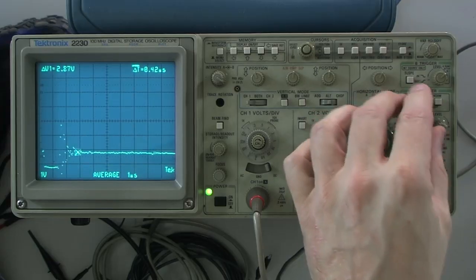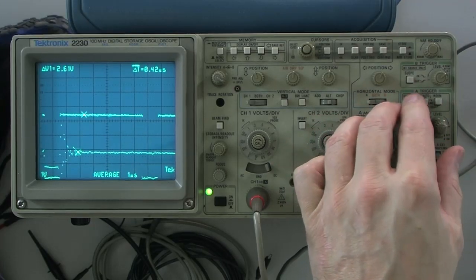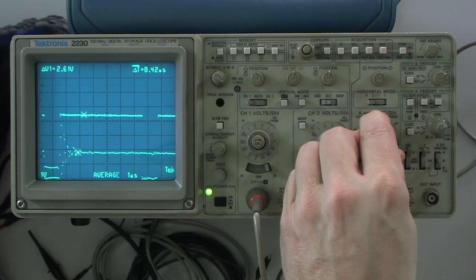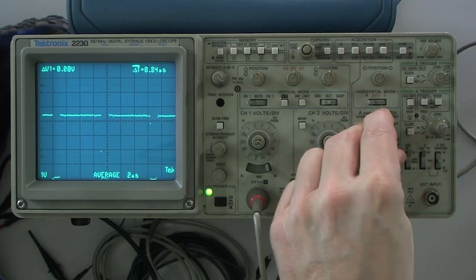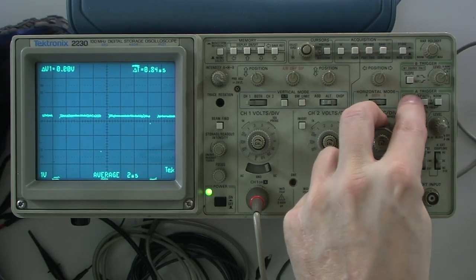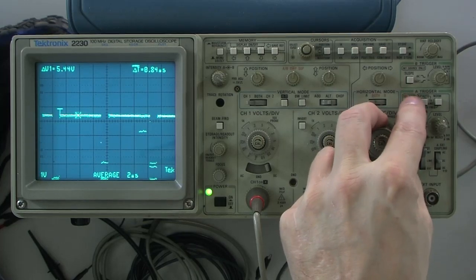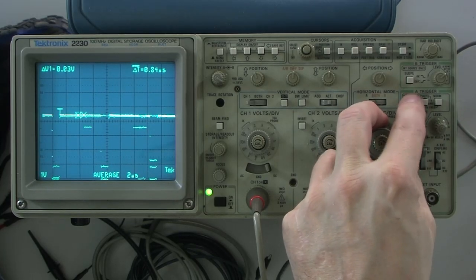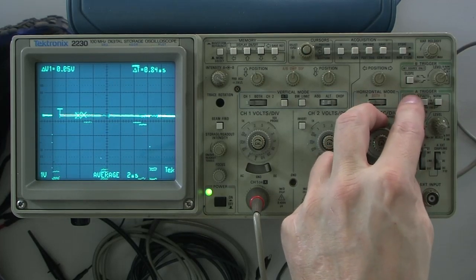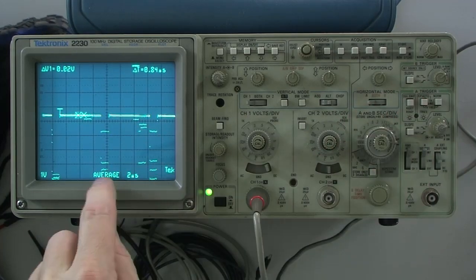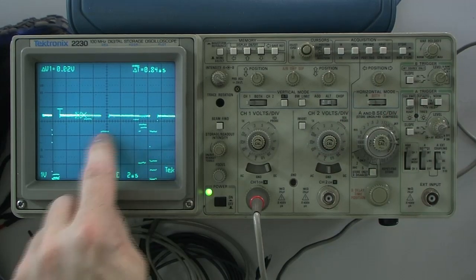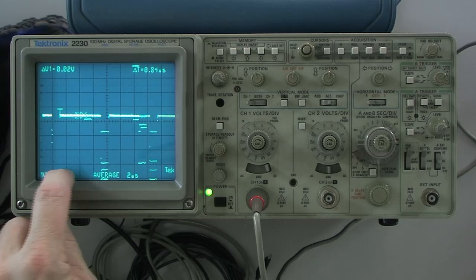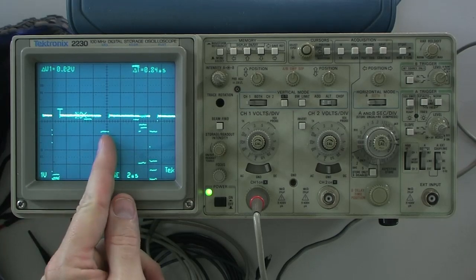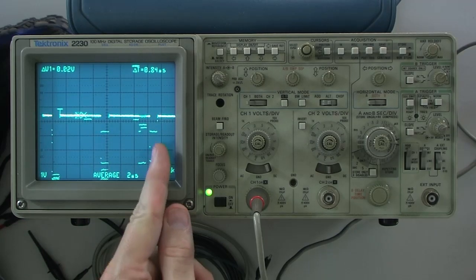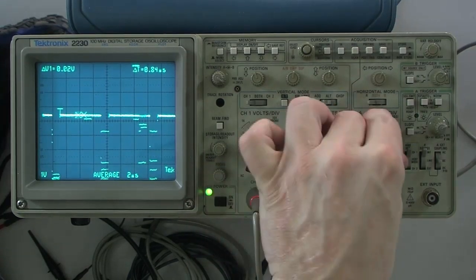If I can, give me a single trace. All right. At this speed, it has to build up an image. There, that's better. See, it's building up an image over time. So it's adding on to the previous store? You're seeing some extra lines come in. Yeah. This is the one trigger that's actually happening. Sometimes this pulse is at a different location because the timing is a little different.